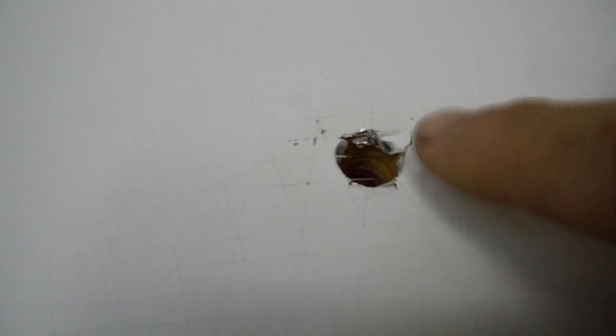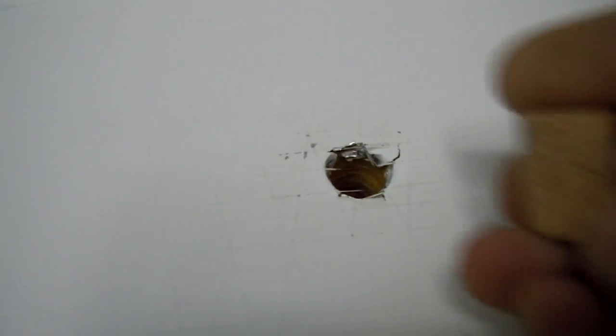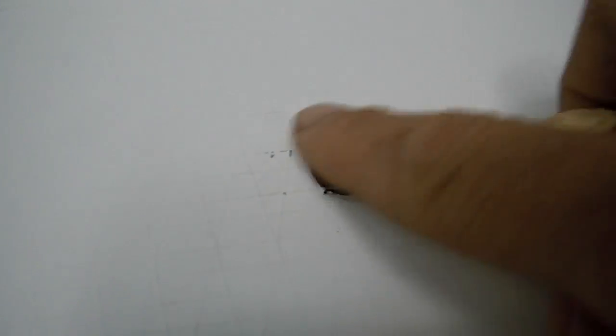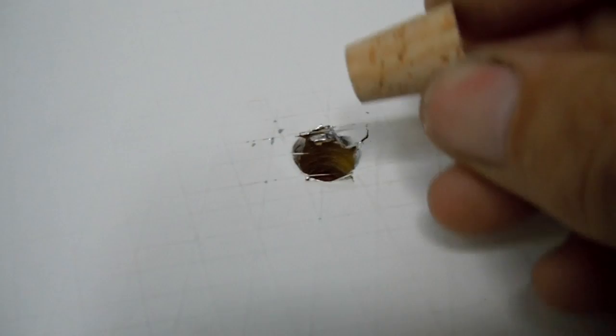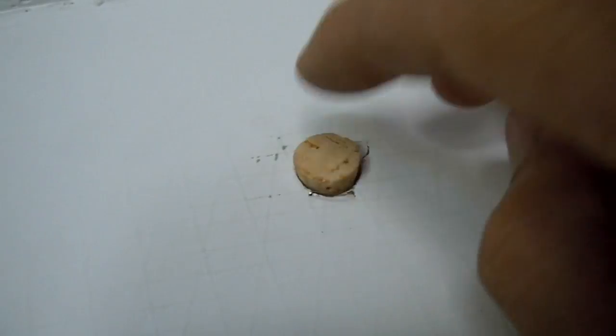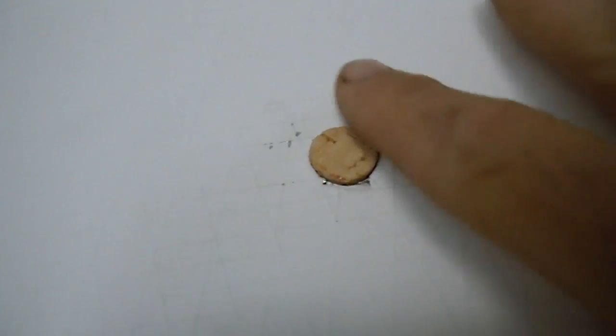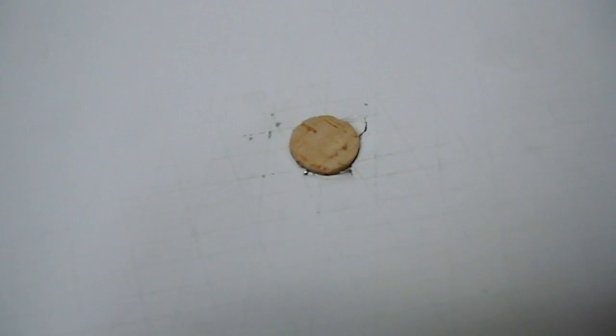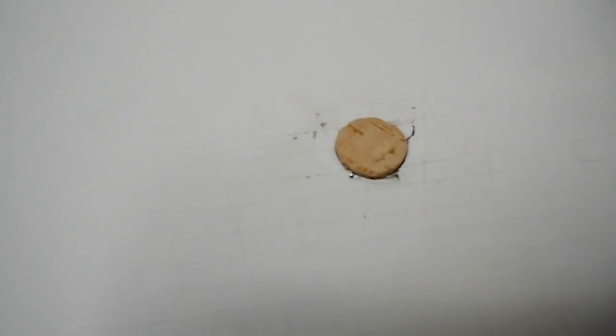If you're wanting to know what to do with the holes that you make in your duct, you could of course tape over them, but in case I want to get back in there again to check the duct again, I just put a piece of cork in there. If you want to put a little piece of tape over it on top of that too that's fine, but this way I can just pull the cork back out when I need to and put the probe back in there for more testing.